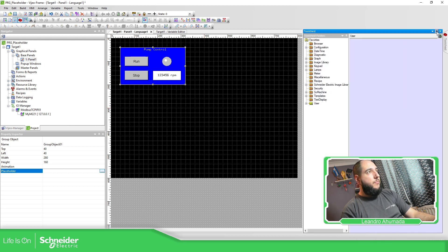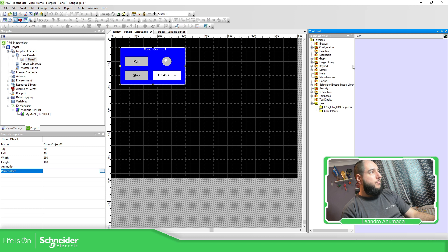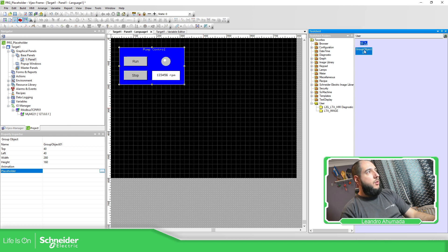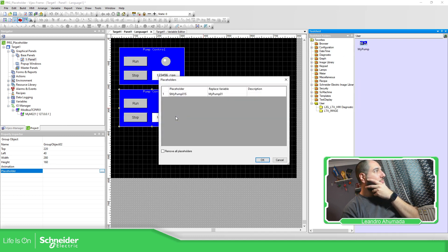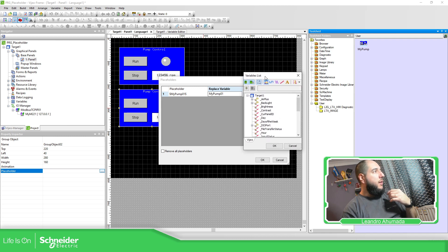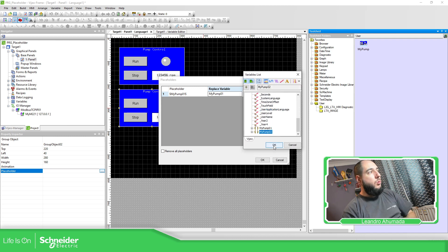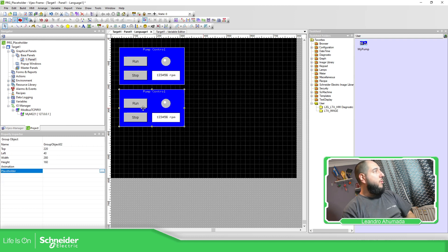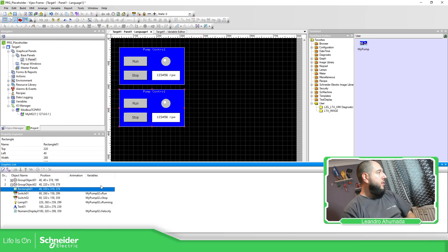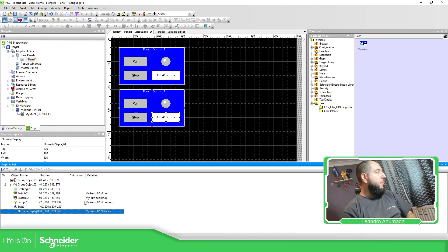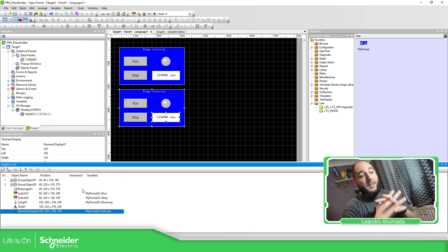The other way is to go to the tool chest and select here in the Users section — drag and drop. So you have here — rename my pump — so you can reuse this element group. Drag and drop it, then it will ask you to change the placeholder. I'm going to change it and use this — O2. So if you access all the elements inside — for example, go to graphic list, object, rectangle — you can see that the variables associated are the number two, and I haven't changed anything at all. This is the easiest and fastest way to speed up the process.